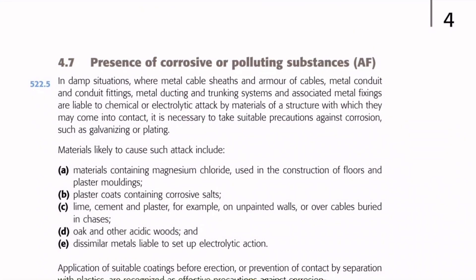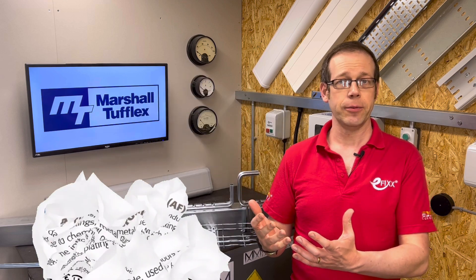One of the downsides to steel containment is that it is highly susceptible to corrosion from atmospheric moisture. For this reason we find this direction in Guidance Note 1 under subheading 4.7, 'Presence of corrosive or polluting substances — AF.' In damp situations where metal cable sheaths and armour of cables, metal conduit and conduit fittings, metal ducting and trunking systems and associated metal fixings are liable to chemical or electrolytic attack, it is necessary to take suitable precautions against corrosion such as galvanising or plating. Although there are different finishes of steel conduit available, it's pretty rare for steel trunking and tray to be anything but galvanised nowadays.